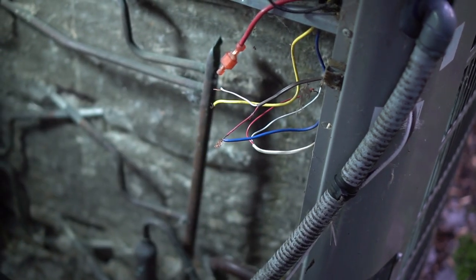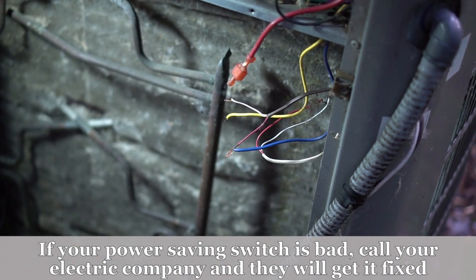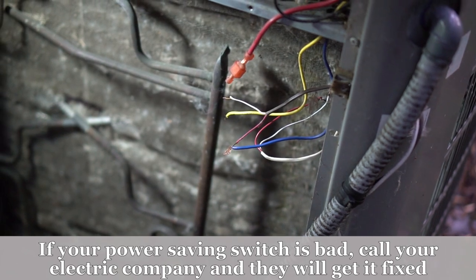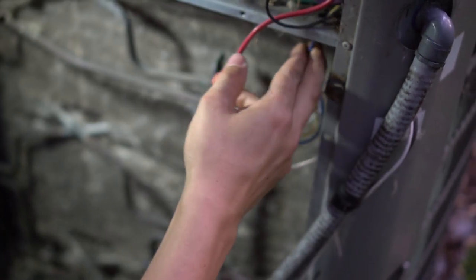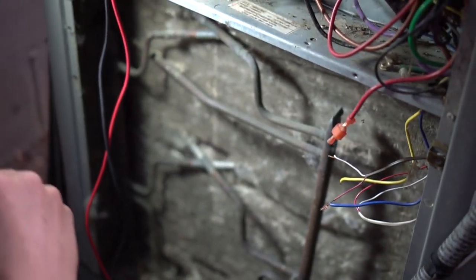Now, if the unit turns on and it works just fine, then you know that your power saver switch is bad. If your unit is still not turning on, then there's something else going on. Maybe you have some other safety switches wired in series with your contactor coil, or the furnace control board is simply not sending power out.